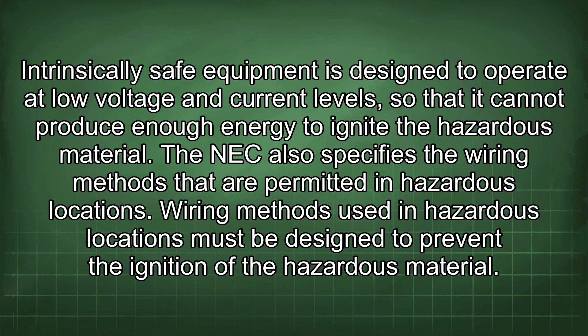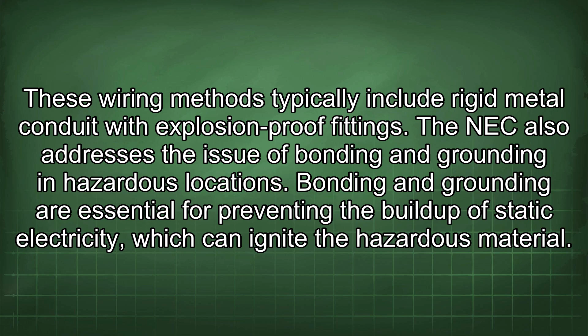These wiring methods typically include rigid metal conduit with explosion-proof fittings. The NEC also addresses bonding and grounding in hazardous locations. Bonding and grounding are essential for preventing the buildup of static electricity, which can ignite hazardous material. This system must be properly installed and maintained to ensure its effectiveness.